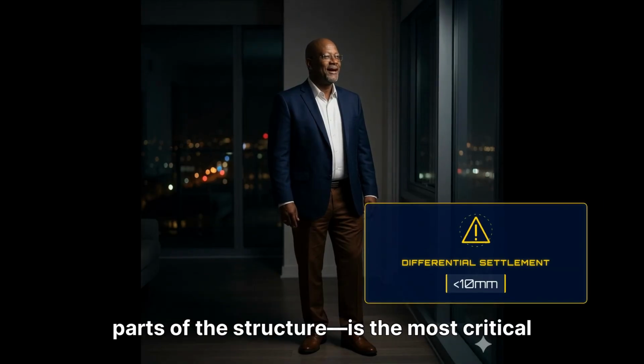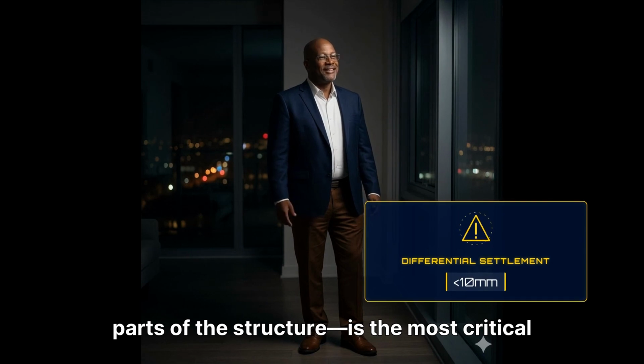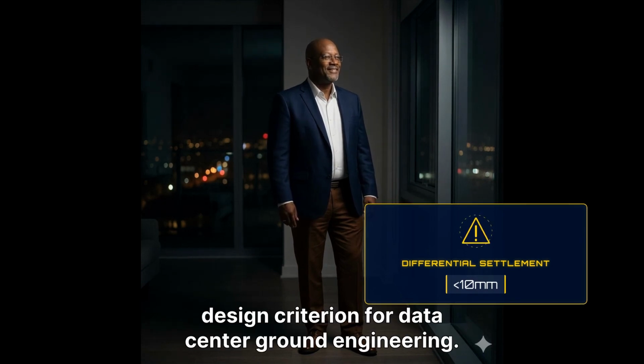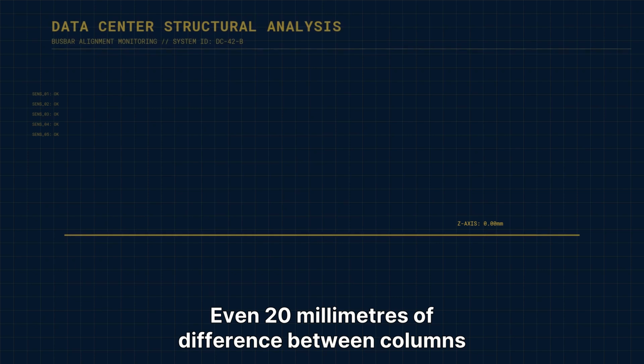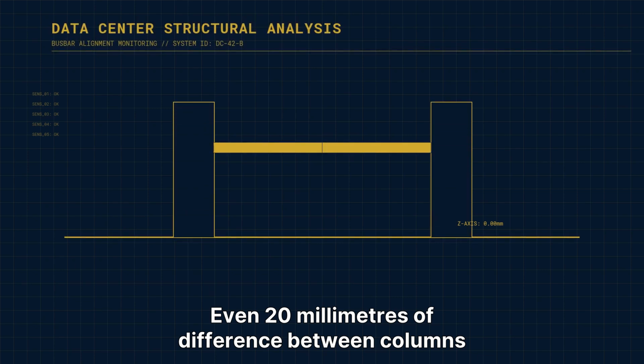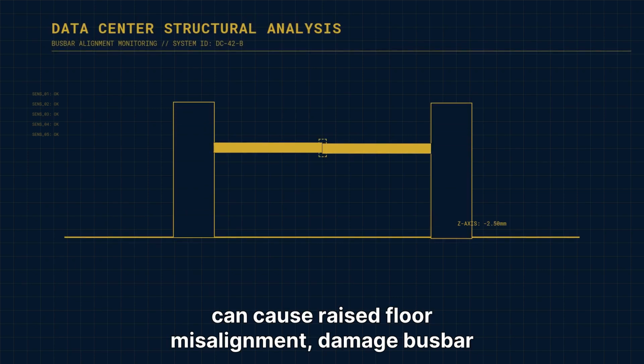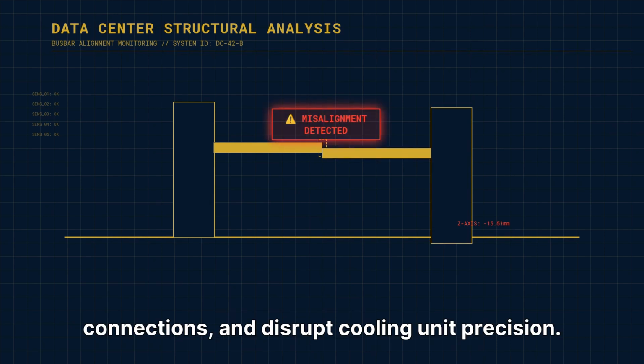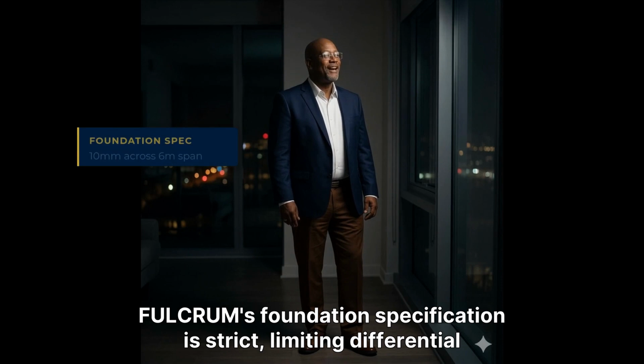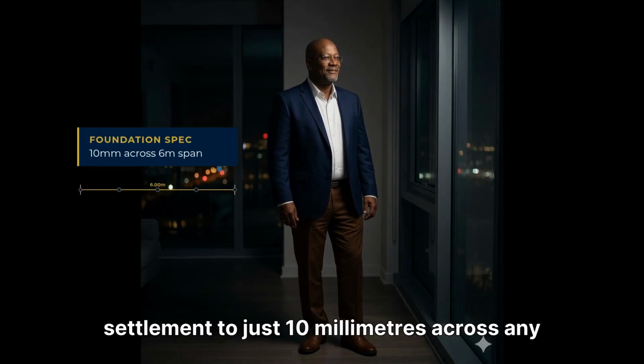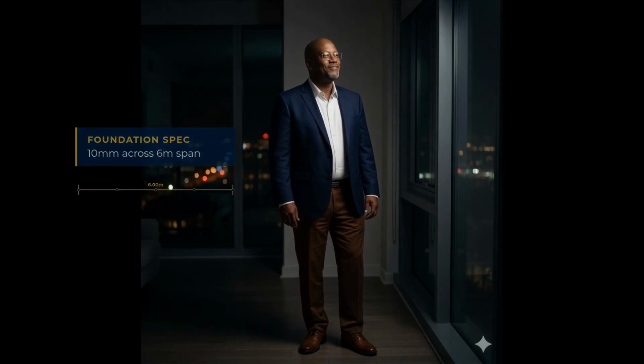Differential settlement, the difference in level between adjacent parts of the structure, is the most critical design criterion for data center ground engineering. Even 20 millimeters of difference between columns can cause raised floor misalignment, damage busbar connections, and disrupt cooling unit precision. FULCRUM's foundation specification is strict, limiting differential settlement to just 10 millimeters across any 6-meter span of the building.